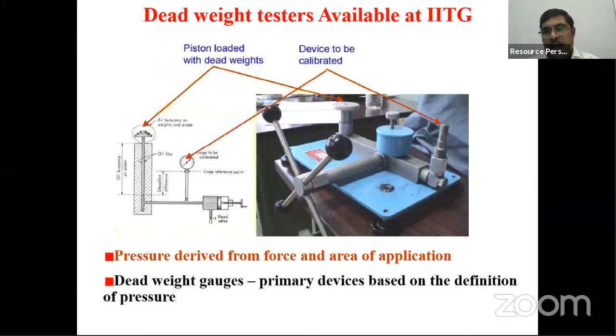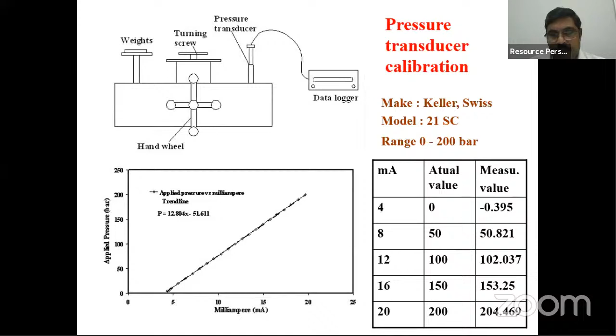Here you can see there is a curve. Most pressure sensors give output in the form of milliamps. For example, when no pressure is applied, the default value is 4 milliamps. In this case, the pressure transducer range is 0 to 200 bar, so at maximum scale you will get 20 milliamps. This is the instrument's output. So you can make a plot between the milliamps and the applied pressure, and from that you get an equation for the pressure output value. This equation can be entered into the data system so that whatever the pressure transducer outputs will be directly converted into pressure.